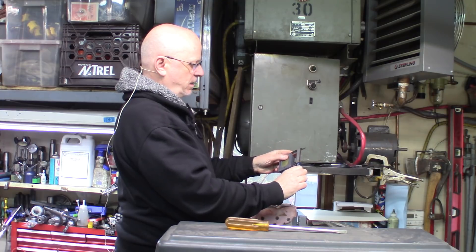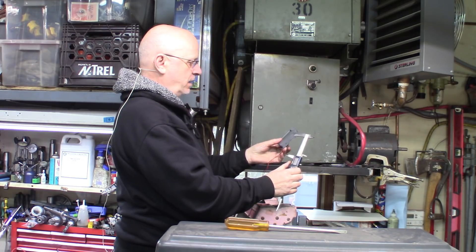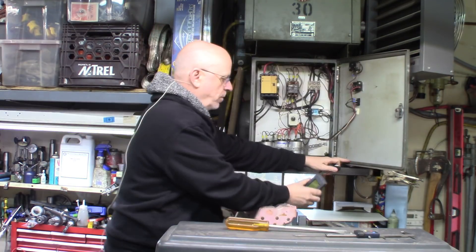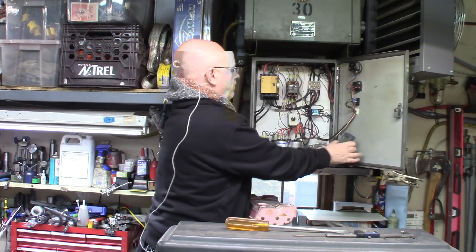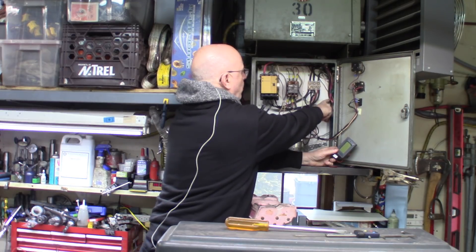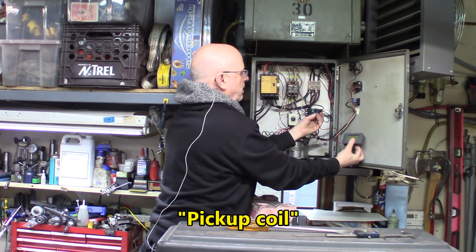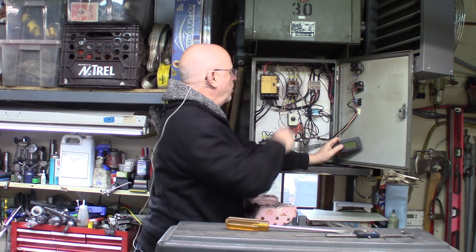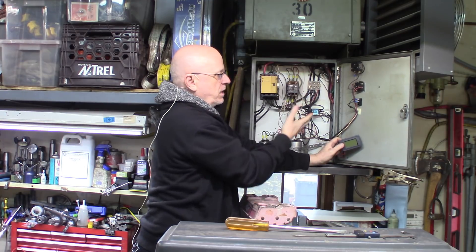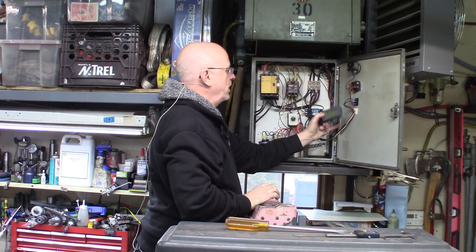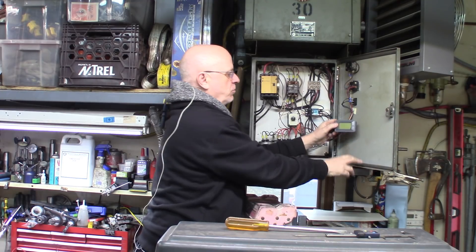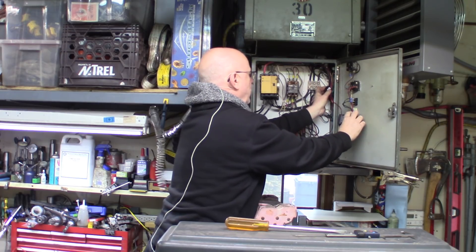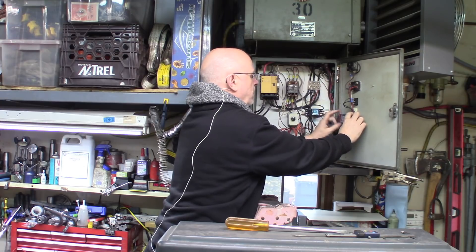I took some measurements of that little enclosed box. By looking inside the box here, I got my inlet wires right there. So I need to slip that little ring around one of those two wires. 220 volts, single phase. The current coming in one is exactly the same current going back into the other branch. So either one of them is a good option to put that little ring around. The little box being there, I'll be able to connect this there and keep the little box right in there.